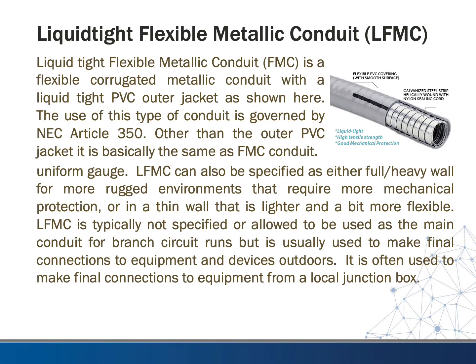Liquid-tight flexible metallic conduit, or LFMC, is a flexible corrugated metallic conduit with a liquid-tight PVC outer jacket. Its use is governed by NEC Article 350. Other than the outer PVC jacket, it is essentially the same as FMC. Like FMC, LFMC can be specified as full or heavy wall for rugged environments, or thin wall for lighter and more flexible applications. LFMC is typically not used as the main conduit for branch circuit runs, but is used to make final connections to outdoor equipment and devices from a local junction box.